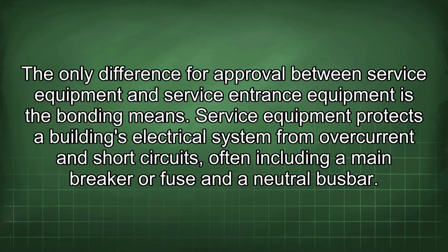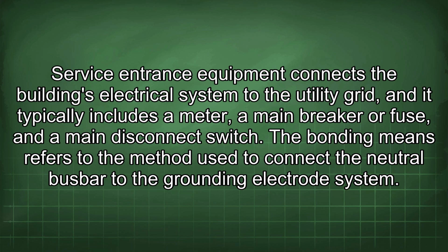The only difference for approval between service equipment and service entrance equipment is the bonding means. Service equipment protects a building's electrical system from overcurrents and short circuits, often including a main breaker or fuse and a neutral bus bar. Service entrance equipment connects the building's electrical system to the utility grid, and it typically includes a meter, a main breaker or fuse, and a main disconnect switch.